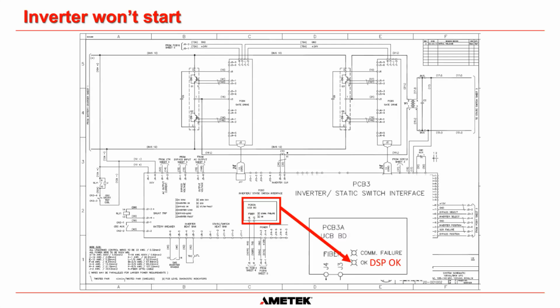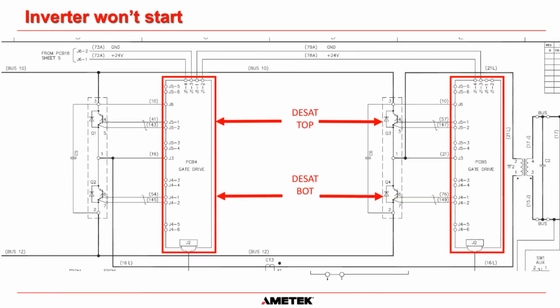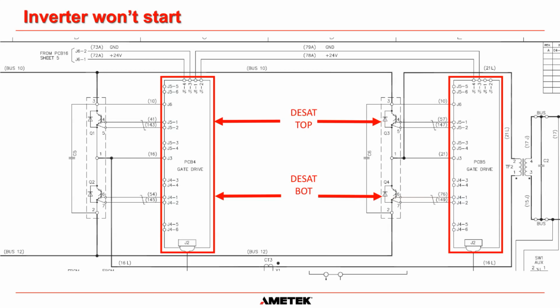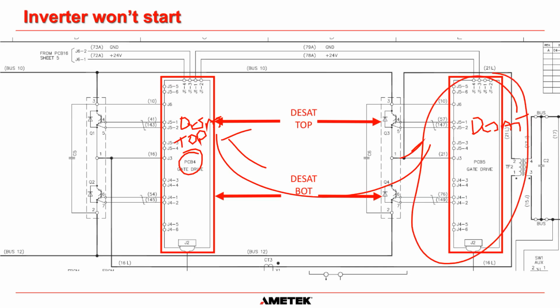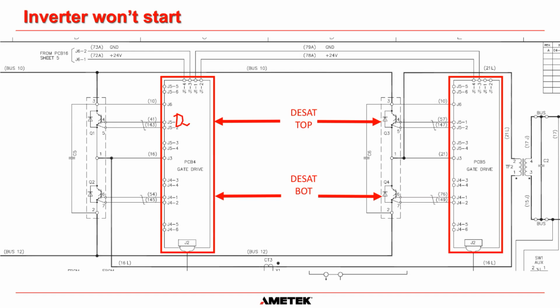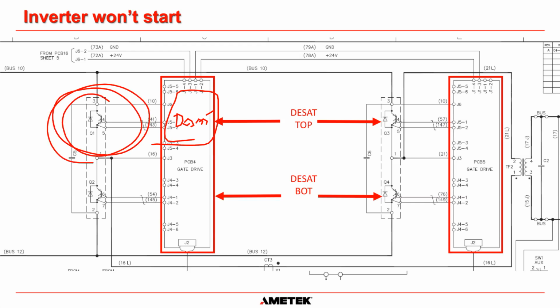You have to have fast blink because we have checks and balances within the software of the system that make sure that the system has all the right parameters to work correctly. As I mentioned, if we have DESAT top or DESAT bottom, you just swap these two boards around. Let's say you had DESAT top on PCB4 and you swapped these boards, and you now had DESAT on this side of the system, then you know the board was the problem. If the DESAT stayed in this position, then you know it is this IGBT Q1, and you would have to replace Q1, and we would usually recommend that you replace the gate drive board as well.